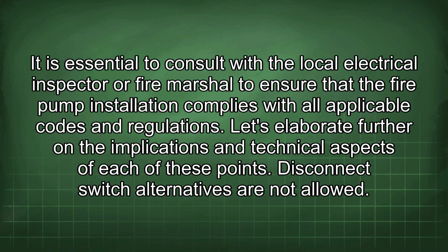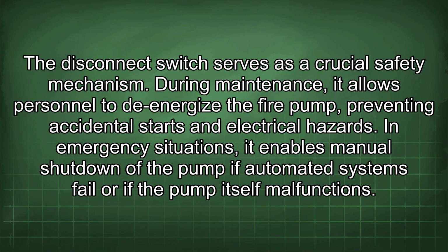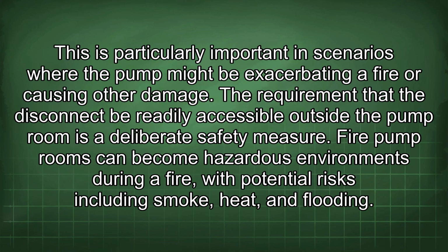Let's elaborate further on the implications and technical aspects of each of these points. Disconnect switch alternatives are not allowed. The disconnect switch serves as a crucial safety mechanism. During maintenance, it allows personnel to de-energize the fire pump, preventing accidental starts and electrical hazards. In emergency situations, it enables manual shutdown of the pump if automated systems fail or if the pump itself malfunctions. This is particularly important in scenarios where the pump might be exacerbating a fire or causing other damage.